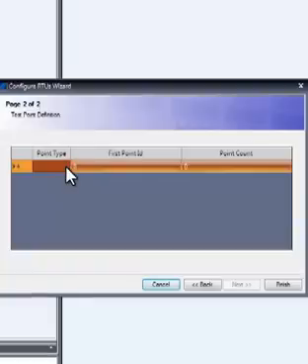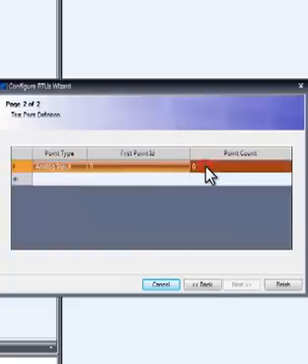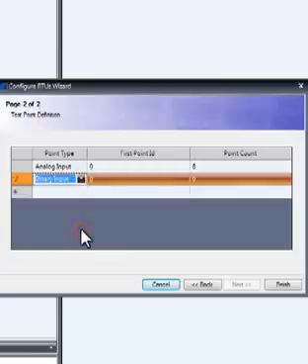All input points at the device should be entered using as many rows as needed. This is not required for protocols with a message having the ability to request all points at the device, such as Class 0 requests for DNP or general interrogation for IEC protocols. Configurations need to be entered for protocols without that capability, such as CONITEL, or for all protocols running the ASE 2000 in RTU simulation mode. It is good practice to complete this step in all cases.